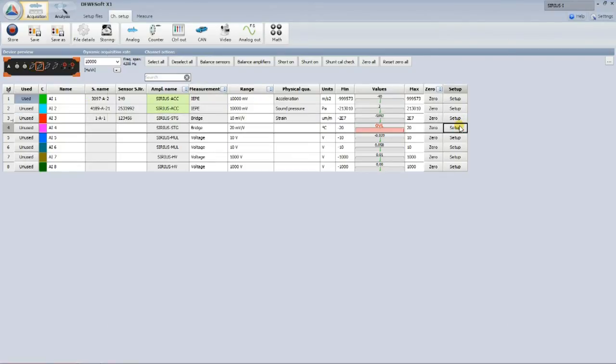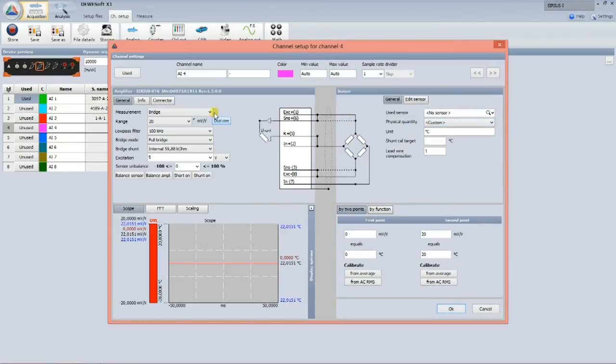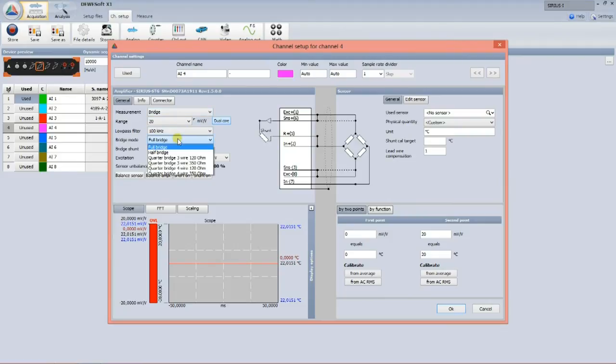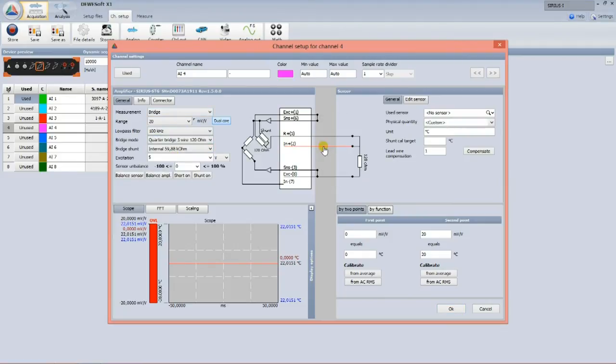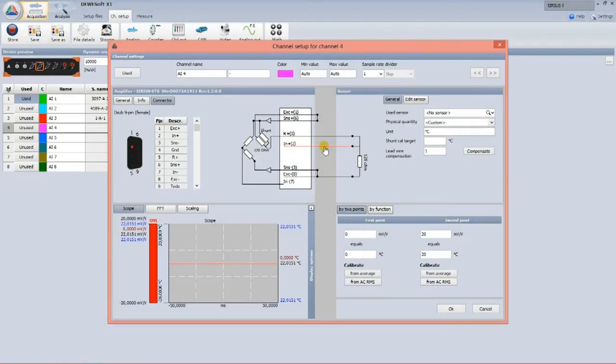In the channel setup, all the connection diagrams are clearly shown for easy wiring. Just set the sensor once within DEWESoft, write it to an inexpensive TEDS chip, and the sensor is defined forever.